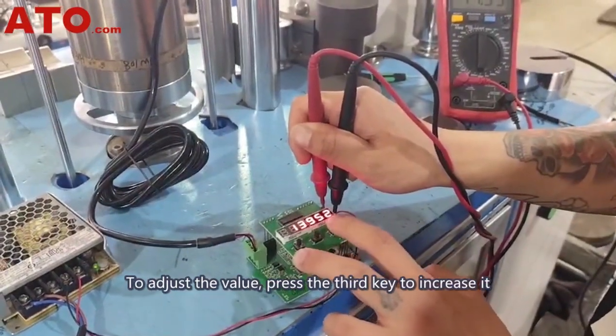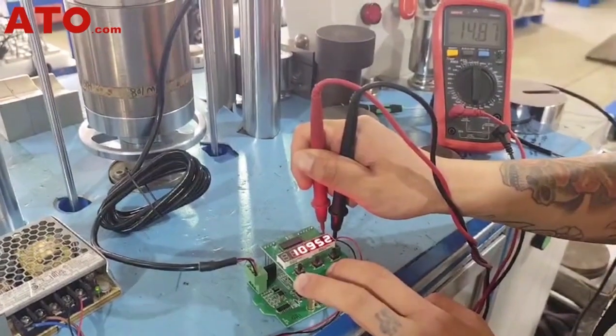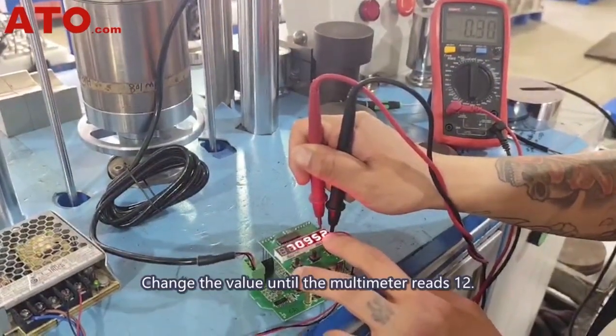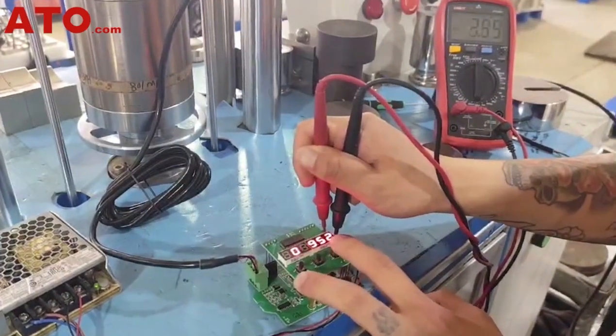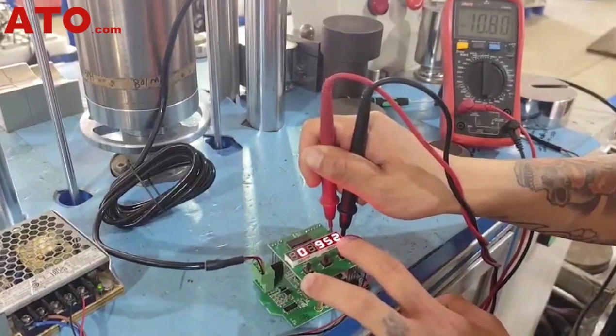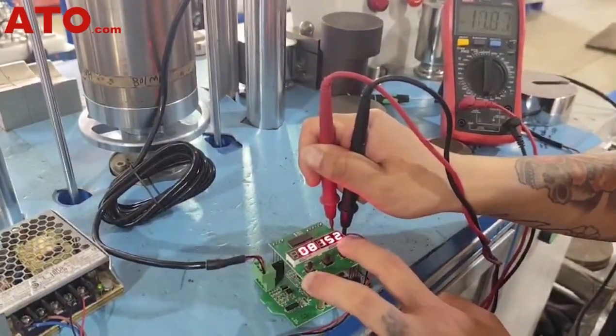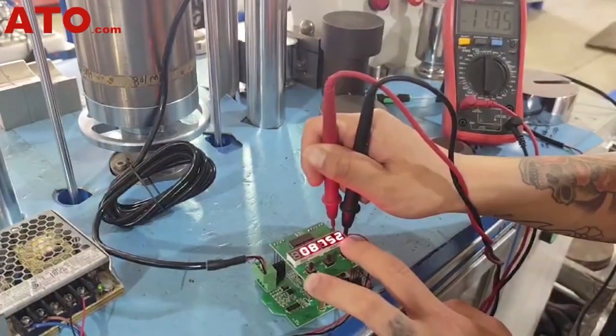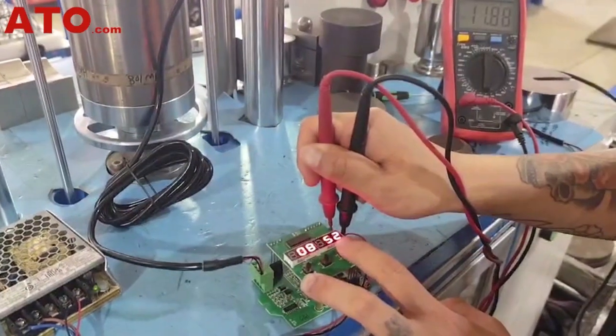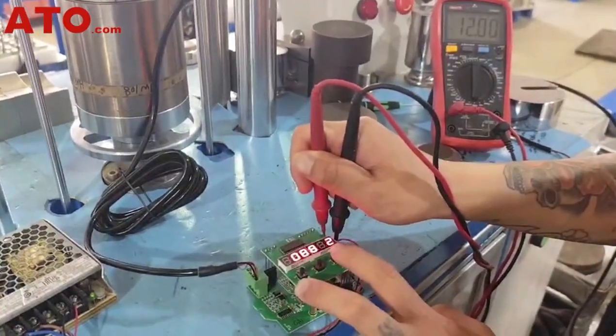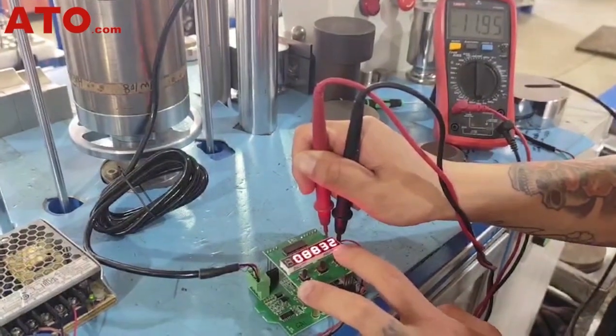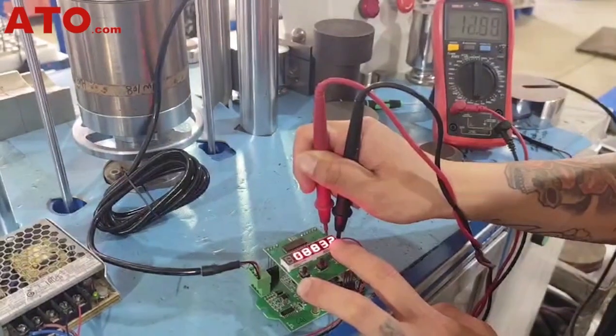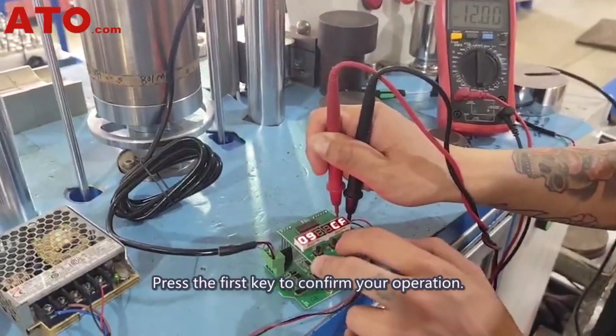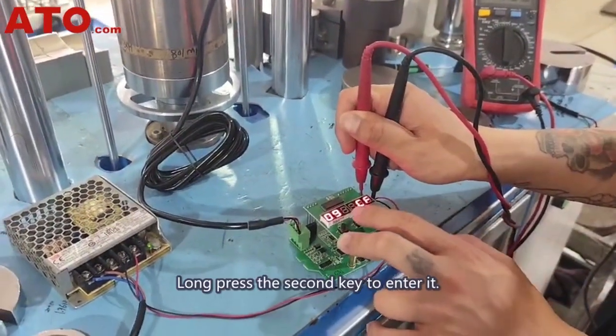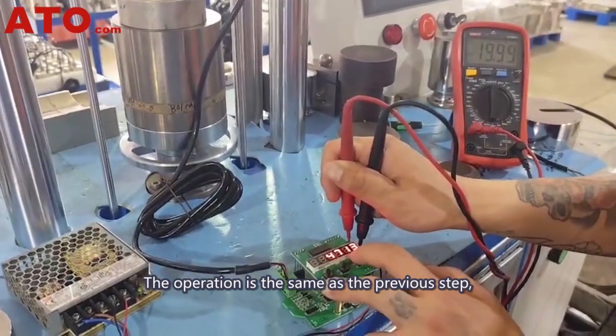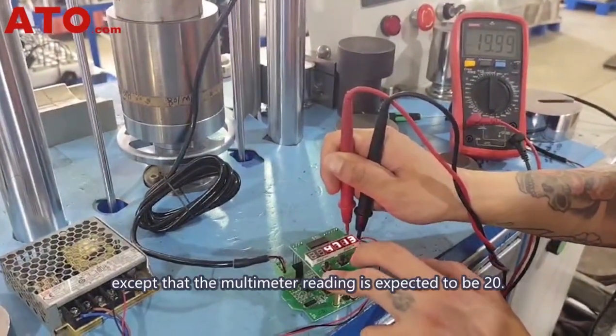To adjust the value, press the third key to increase it, and the second key to change digits. Change the value until the multimeter reads 12. Alright, that's gonna do. Press the first key to confirm your operation. Then the next parameter is 09CF. Long press the second key to enter it. The operation is the same as the previous step, except that the multimeter reading is expected to be 20.